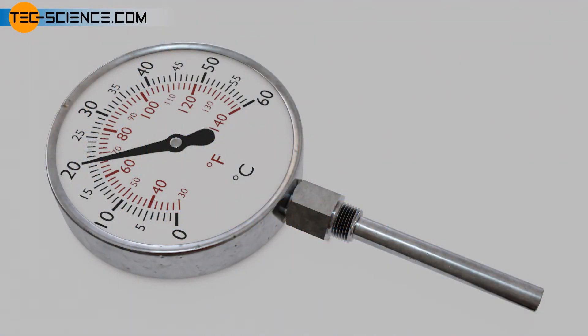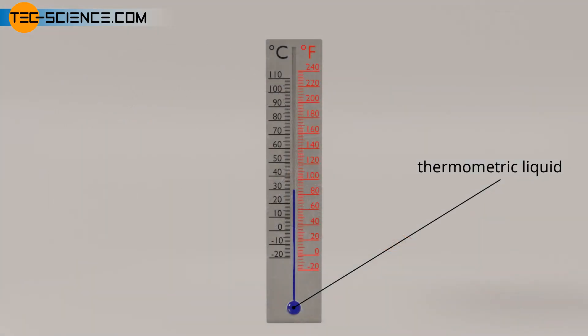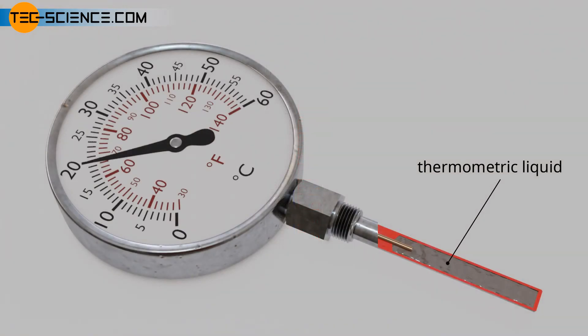In liquid-in-metal thermometers, also referred to as liquid-filled thermometers, a liquid is used as a thermometric substance in the same way as in liquid-in-glass thermometers. However, it is not the thermal expansion of the liquid that is measured, but rather the increase in pressure that goes hand-in-hand with an increase in temperature when the liquid completely occupies a closed volume.